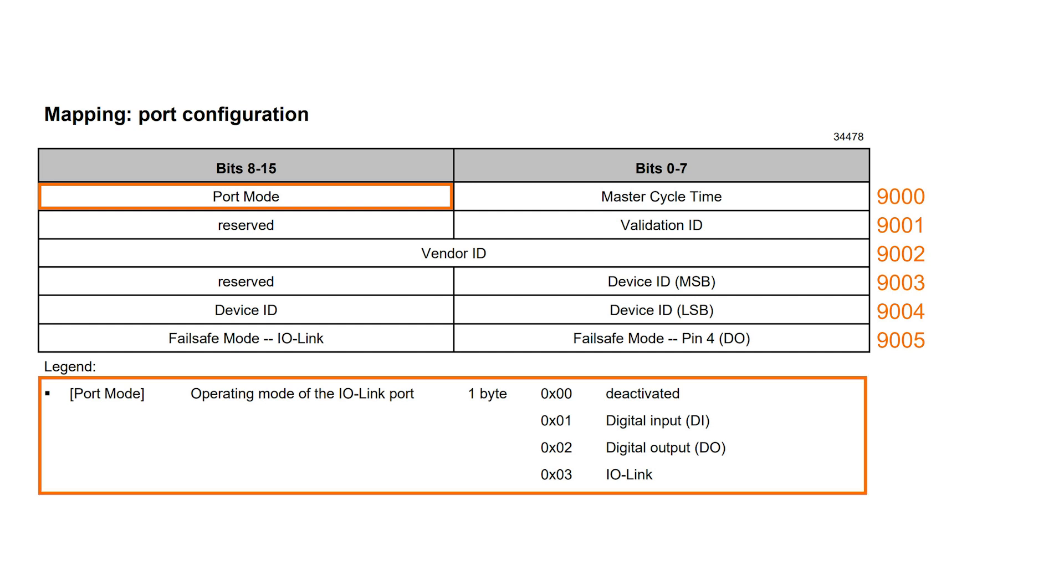We start with the setting of the port mode. For this, we look at the legend under the mapping table for the port configuration in the device manual. The port can be deactivated, used as digital input or output, or even set to IO-Link functionality. To use port 1 as IO-Link port, we have to write the value 3 to the referring register address.